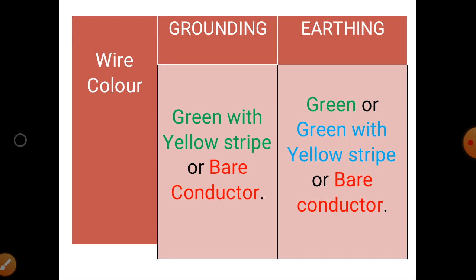And what are the wires? Already I said that when the neutral point is connected to the ground, that is called grounding, and when the metal body is connected to the ground, that is called earthing. So between the neutral point and the ground we use a conductor. So what is the color of the wire used for connecting the neutral point to the ground, and also the metal body of the equipment to the ground? For grounding purpose we use green wire with yellow strip, or otherwise a bare conductor. Bare conductor means a pure copper conductor without any insulation. For earthing purpose we can use green or green with yellow strip wire or a bare conductor. So these are the colors of wire used for grounding and earthing purpose.